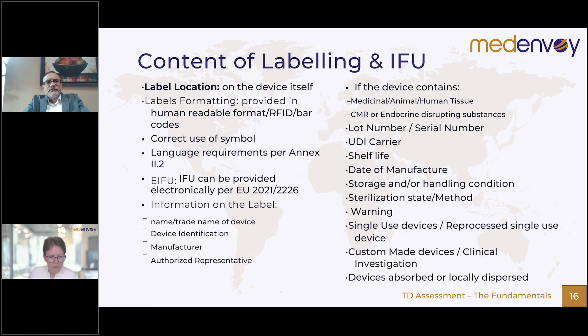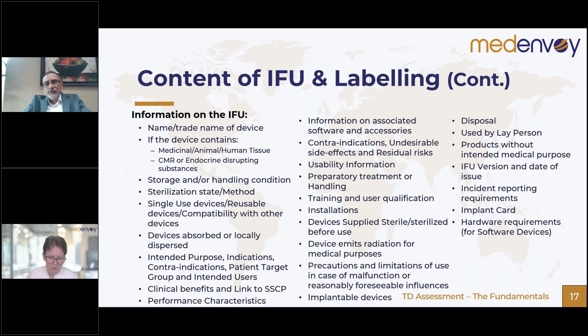So technical documentation reviewers are not assuming anything. They go through what is in the GSPR and where in your label and IFU that information is covered. So it's fundamentally important that we put a lot more emphasis on that. All the details that are there, I'm not going to read out because of time constraint, but you can go through this information on the slide. Most importantly on GSPR, they will be checking against each listed requirement, and if it is not applicable, they will check if it has been justified in your GSPR or technical documentation why a certain requirement is not applicable and what your reasons are. So that's one of the key elements.